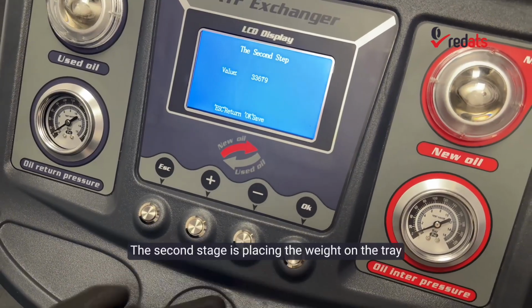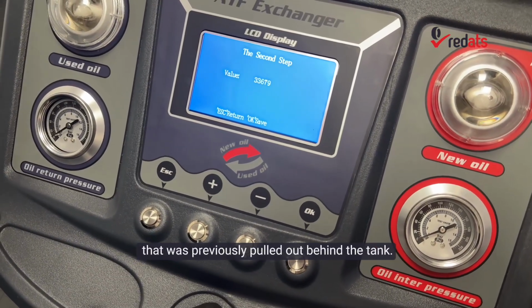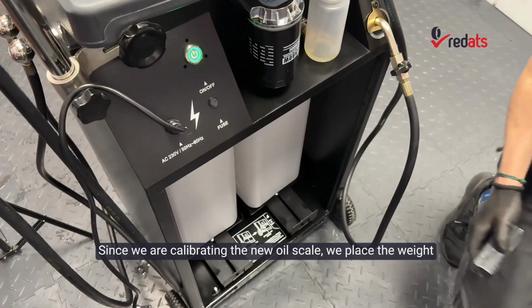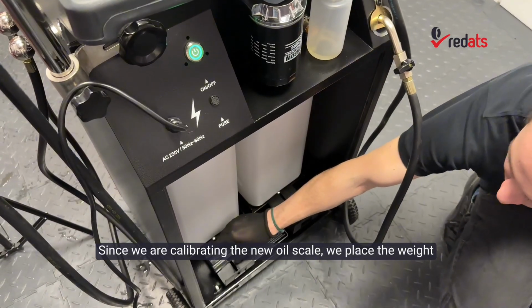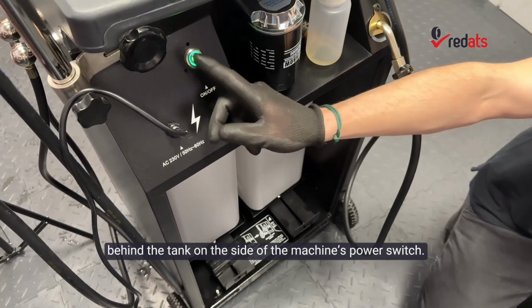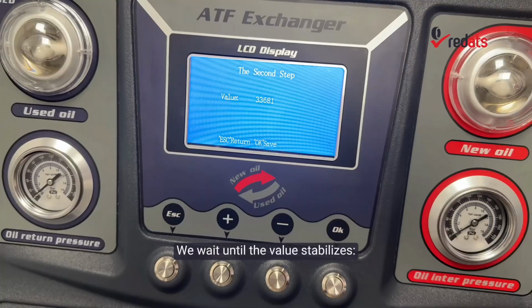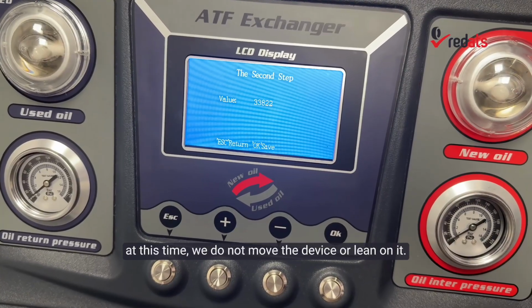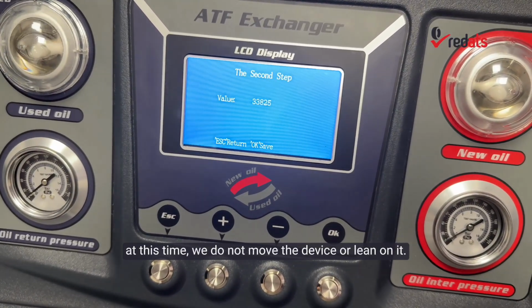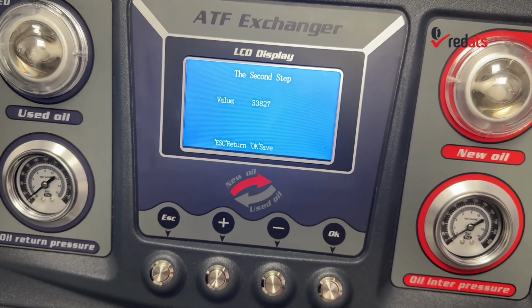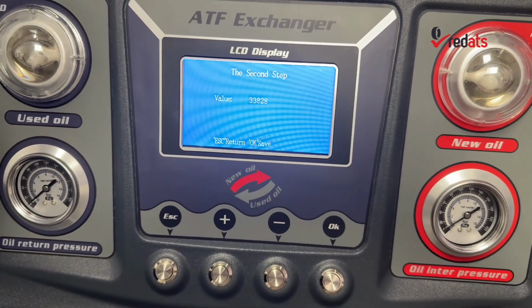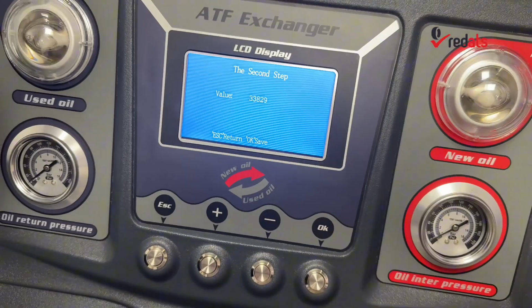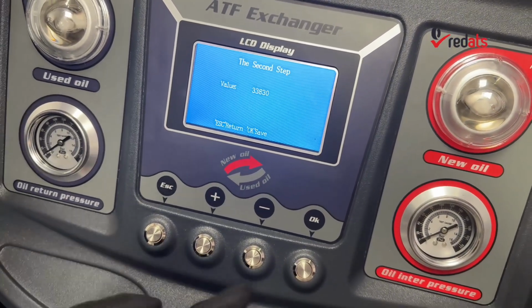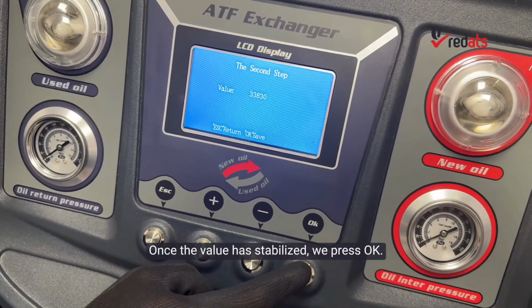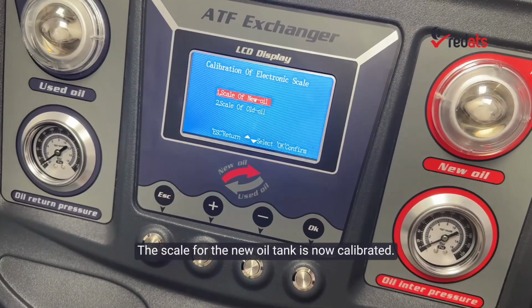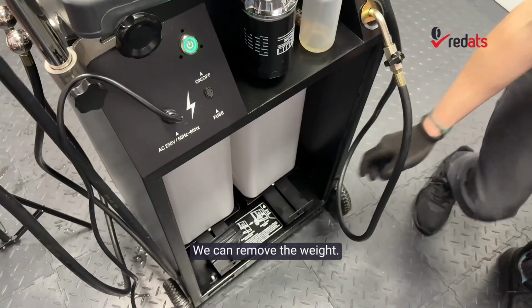The second stage is placing the weight on the tray that was previously pulled out behind the tank. Since we are calibrating the new oil scale, we place the weight behind the tank on the side of the machine's power switch. We wait until the value stabilizes. At this time, we do not move the device or lean on it. Once the value has stabilized, we press OK. The scale for the new oil tank is now calibrated. We can remove the weight.